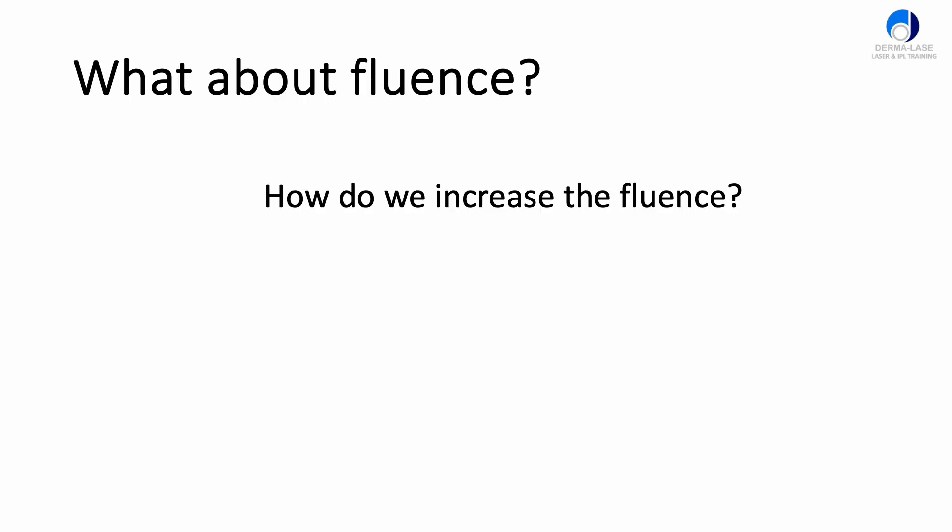How do we increase the fluence in a laser or an IPL? Let's go back to the definition of fluence. Fluence measured in joules per square centimeter is simply the energy from the laser applied to the skin surface divided by the spot size area that you're firing at the skin surface. This means there are two ways to increase the fluence.